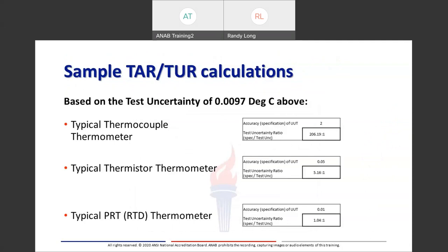If I take this same uncertainty and replace resolution with a thermocouple type thermometer device, you can see that the uncertainty best-case scenario goes up to 0.06 degrees C. Looking at test accuracy ratios: considering a test uncertainty of 0.0097, a typical thermocouple thermometer with an accuracy of plus or minus 2 degrees gives a test uncertainty ratio of over 206-to-1. A different device — a digital thermometer with an accuracy specification of 0.05 — gives a test uncertainty ratio of 5.16-to-1. And for a higher-end sensor like an RTD or PRT with an accuracy of 0.01, we've got about a 1-to-1 test uncertainty ratio.